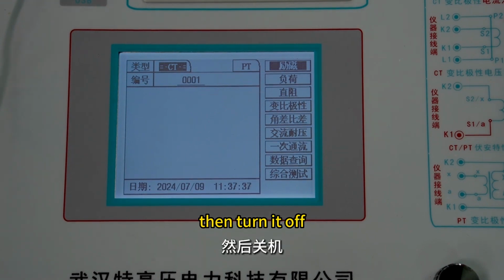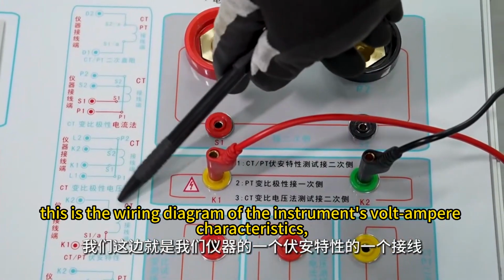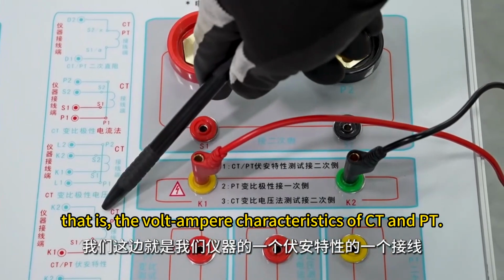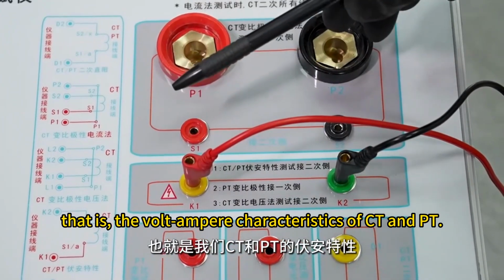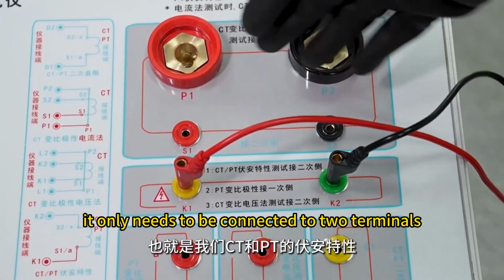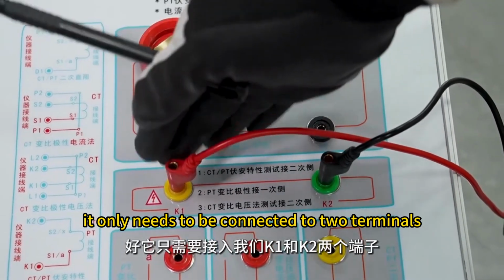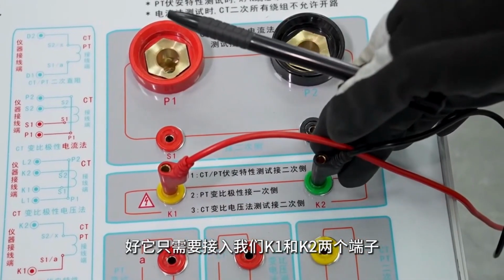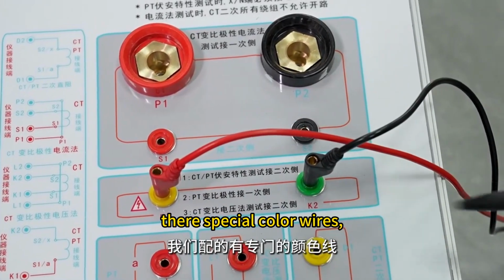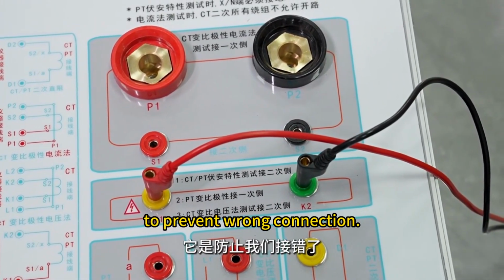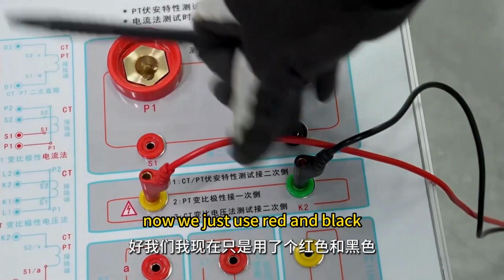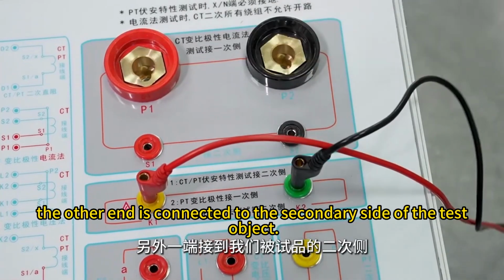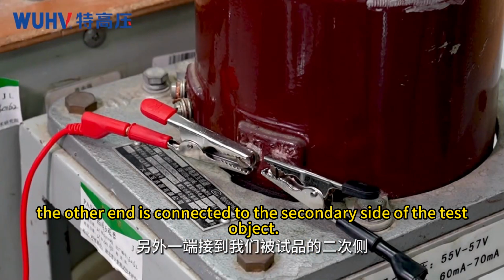Then turn it off. This is the wiring diagram of the instrument's volt-ampere characteristics, that is, the volt-ampere characteristics of CT and PT. It only needs to be connected to two terminals, K1 and K2. The color is up to us. There are special color wires to prevent wrong connection. Now we just use red and black. The other end is connected to the secondary side of the test object. After connecting the wires, turn on the power switch.